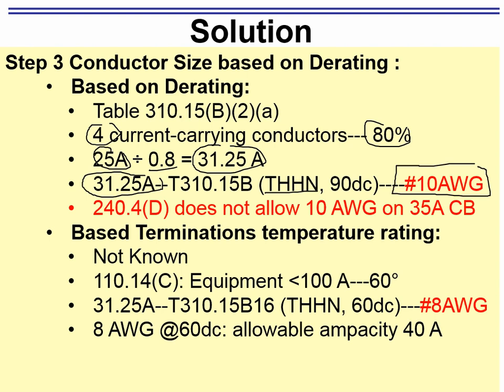We have number 10. Okay, so I did two calculations. One came up with number 8, one came up with number 10. Which one would you use? The largest of the two, number 8. And you can't use number 10 on a 35 amp breaker. Remember, there's a small conductor rule that says number 10 is limited to 30 amps. But it doesn't really matter.